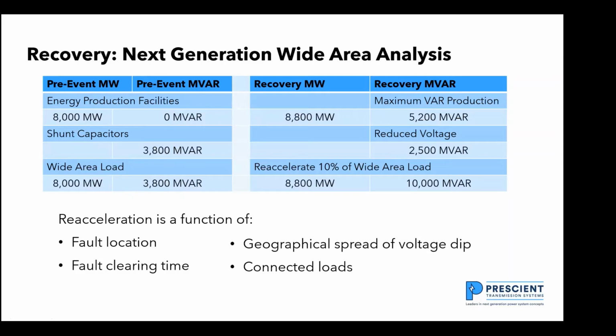When a fault occurs, the recovery megawatts could be 8,800. So the recovery megawatts are 10% higher than the pre-fault load. But the machines can produce 5,200 MVAR. They have the capability of producing 5,200 MVAR in pre-event, but we were taking capacitors rather than machines providing it. When the voltage drops because of the transient that occurred, the MVAR capability of the capacitors is reduced. So I went from 3,800 MVAR of capacitance to 2,500. So that says as soon as the fault is cleared, in the simulation I have here, I have 7,700 MVAR available for re-energizing and reaccelerating motors. The problem that we come up with is under normal conditions, the demand was 3,800 MVAR. If I'm just trying to reaccelerate 10% of my load that's out there, the new MVAR demand is 10,000.